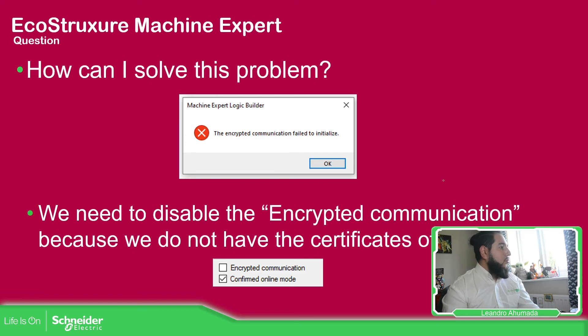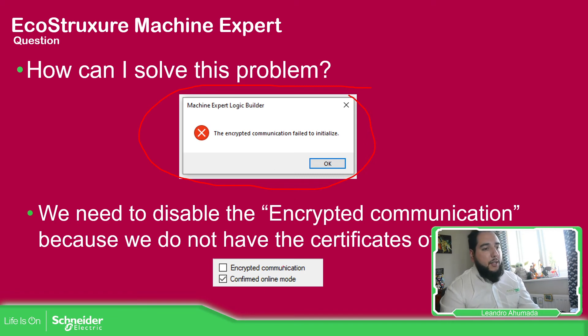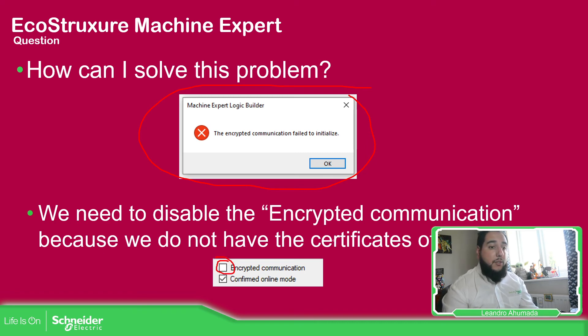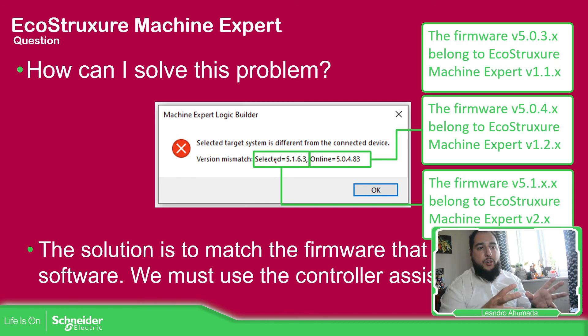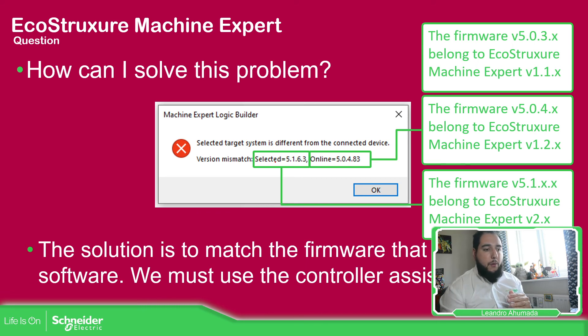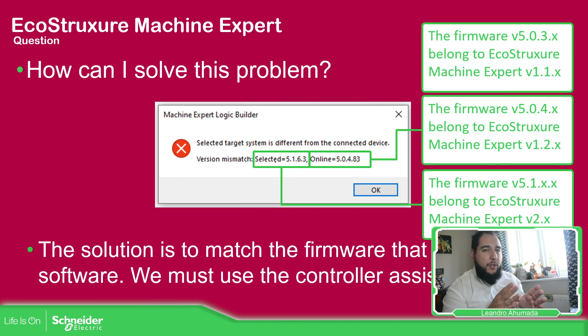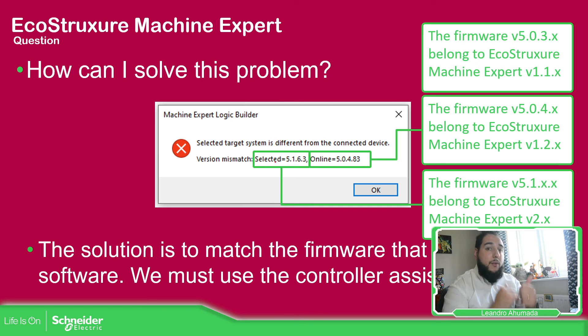You may see this message: 'Encrypted communication failed to initialize.' In that case, we just need to uncheck Encrypted Communication and that will sort out the issue. The other common problem is when you have an application in your project and you're trying to log in to the controller, but it doesn't allow you because you have a mismatch — and probably it's not a mismatch of the M262 reference but a problem of the firmware. You will need to change the firmware as shown in the previous videos.